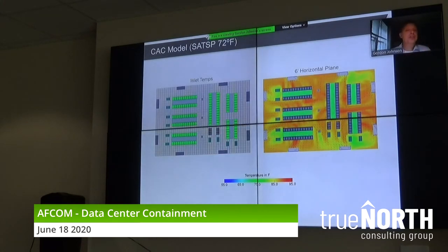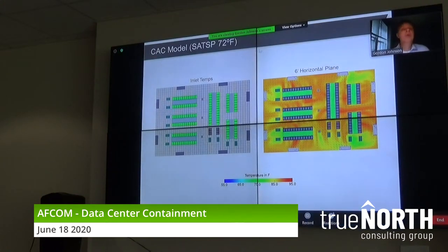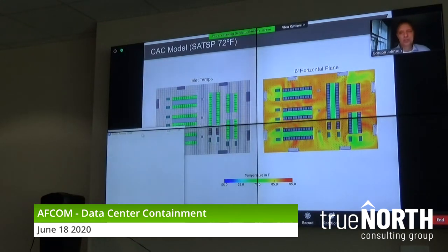Let's try to raise some temperatures, and here's where we do our airflow optimization, or our cooling optimization. Here's where we really start to save you money in the data center. Same data center, I turn all CRAH units back on, so we're all running at 100% fan speed. I've taken my supply air temperature, which was 62, and raised it to 72. Look on the left at my inlet temperatures. They're 72, 73 degrees, consistent across the board.